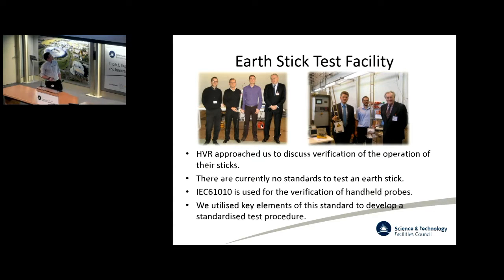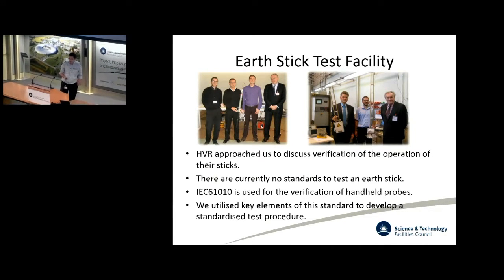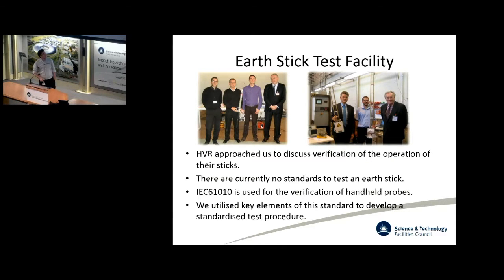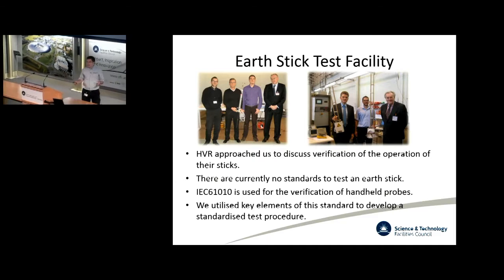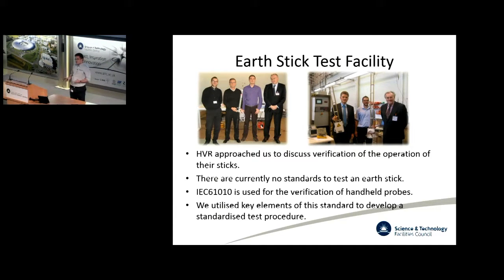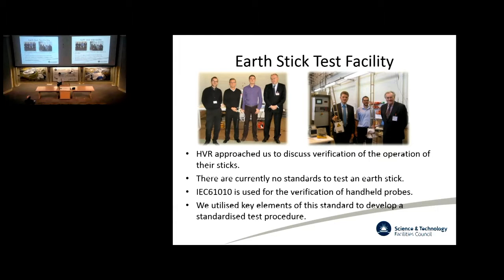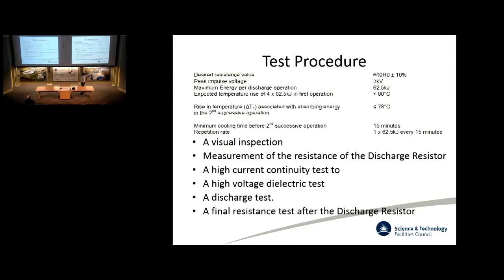The closest standard we could find is IEC 61010, which is used for the verification of handheld probes for high voltage measurement. Mostly it's about making sure that the probe is in good condition, that there are no breaks, that there's a good contact to ground, that there's sufficient probe surface area, and that the fault current you get when you use the stick is not excessive and will not cause damage to the stick. We wrapped those up in a standardized test procedure that we wrote for ourselves. So what's in this standardized test procedure?